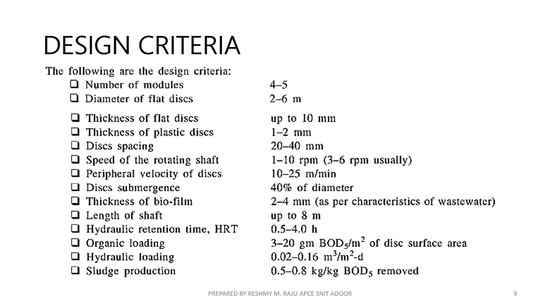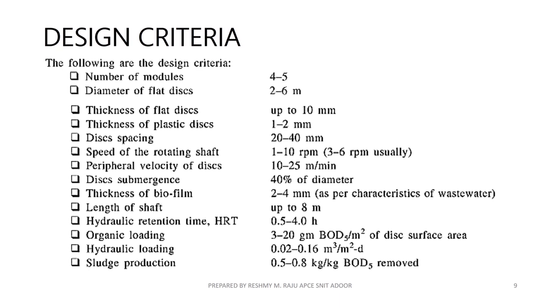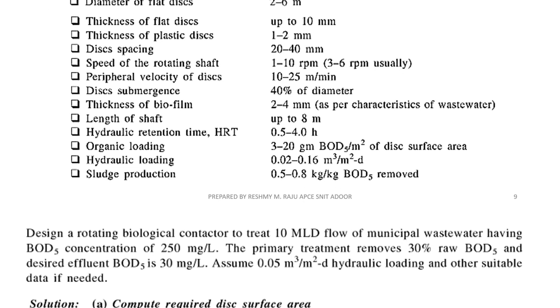The design criteria include several key parameters: the number of modules, the diameter of the flat disc within a particular range, rotational speed of 1 to 10 rpm (typically 3 to 6 rpm), biofilm thickness of 2 to 4 mm (which varies with wastewater characteristics), and shaft length up to 8 meters depending on the manufacturer's standard module size.